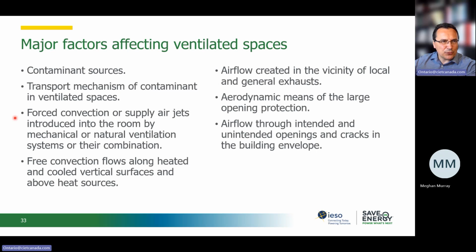And then we design the system so that we force the air introduced into the space to direct the sources of contamination towards the exhaust. We use free convection flows that can carry the contaminants towards the exhaust.